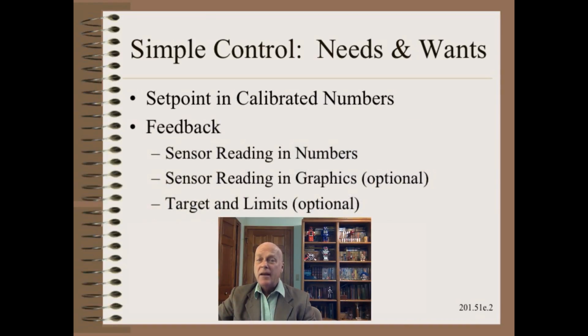Also, for the same reasons of reproducibility and trustworthiness, we need a sensor feedback reading in numbers. The feedback reading also needs to be calibrated in the same engineering units as the set point, as well as calibratable per instructions in the service manual.